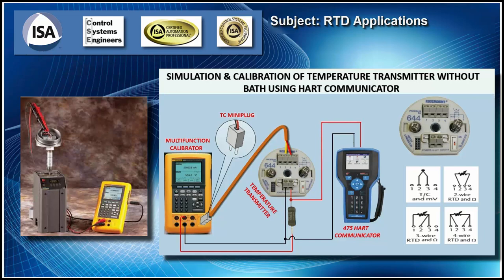This is a thermocouple, and it's a K-type thermocouple. We know it's K because it's yellow and it's red. And so it's a thermocouple going in. And we can simulate the thermocouple by plugging it into a multifunction calibrator, and then we send out the signal, which gives us a voltage proportional to the temperature, and we can calibrate that way. With an RTD, you just connect up to the RTD the same way, and it'll simulate an RTD for you, and you can calibrate for your temperature.